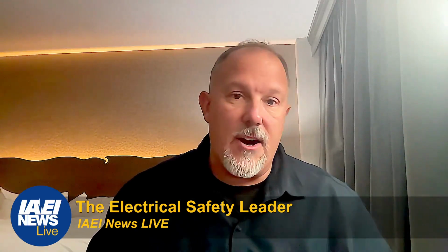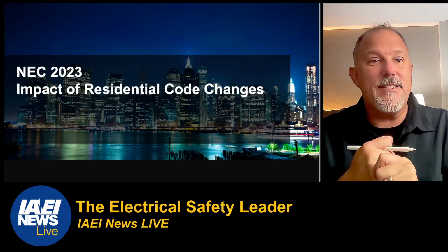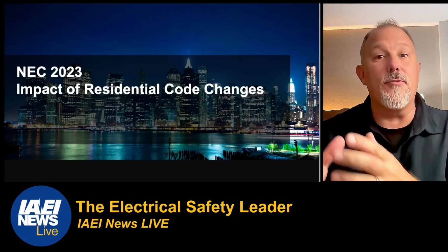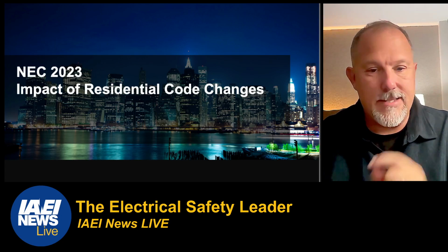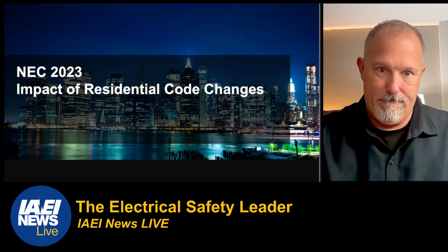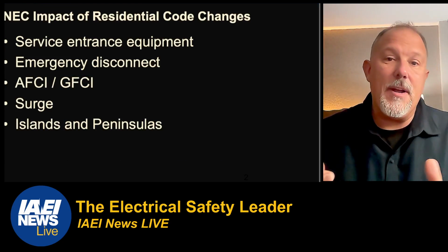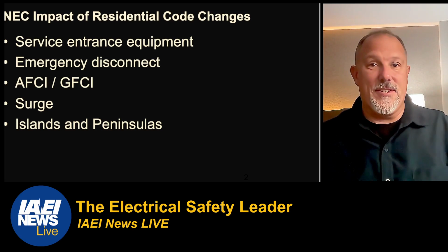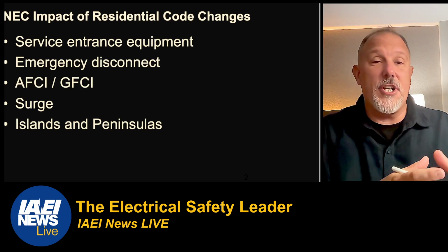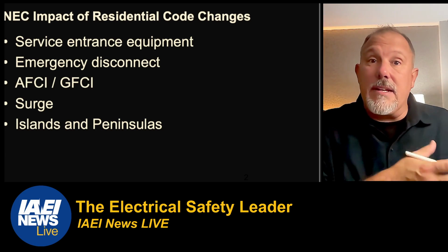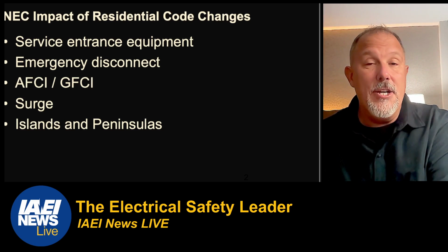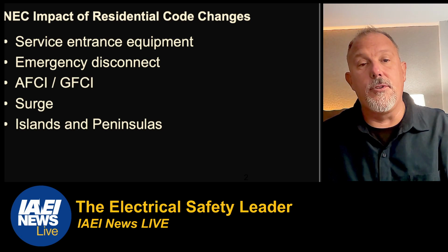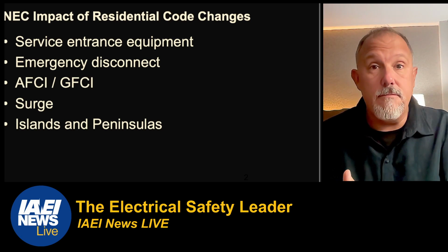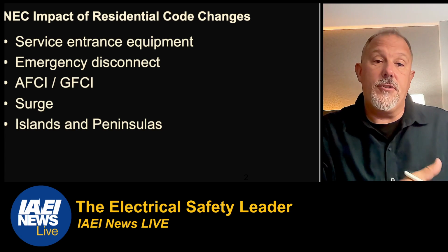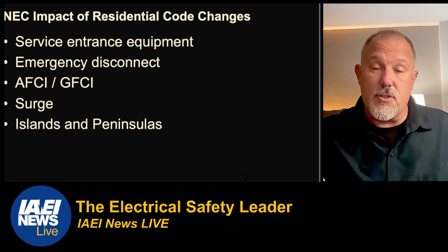So let's kick this off by taking a look at 2023 code changes that impact residential applications. A few of the areas: service entrance equipment, where we saw changes during the 2017, 2020, and into the 2023 code cycle. Areas of discussion include the six disconnect rule and surge requirements. We saw the 2020 code have new surge requirements that directly impact service entrance equipment.